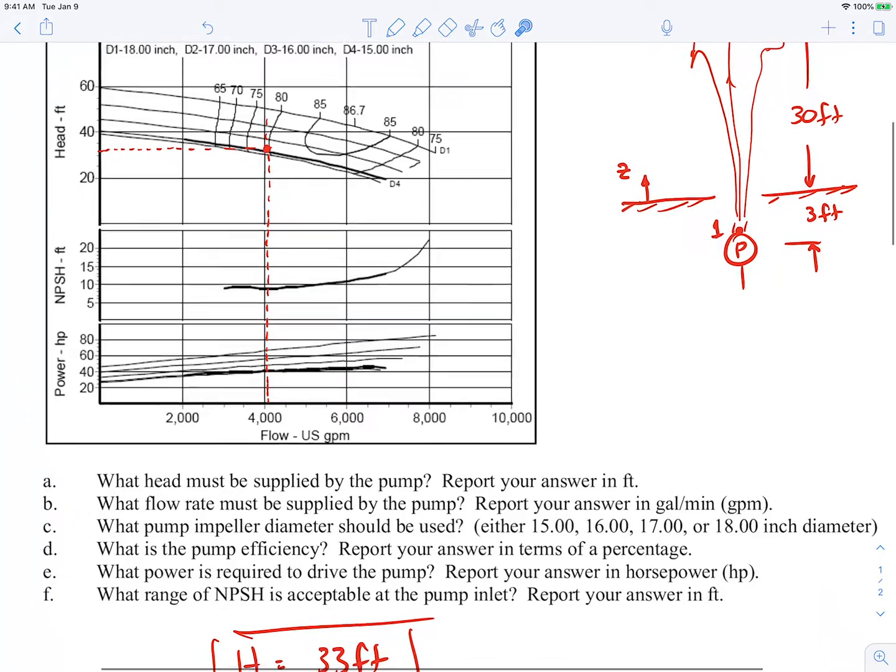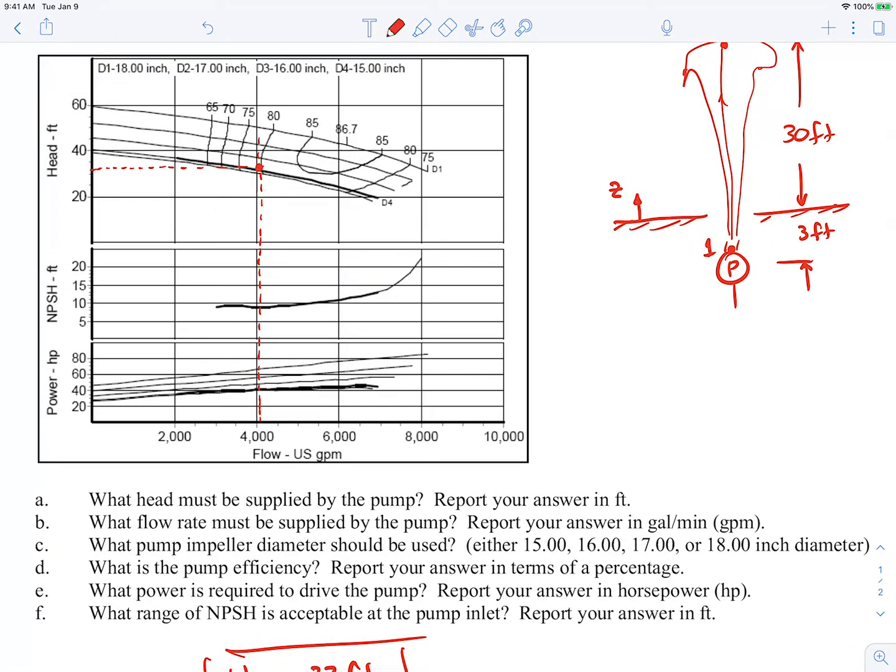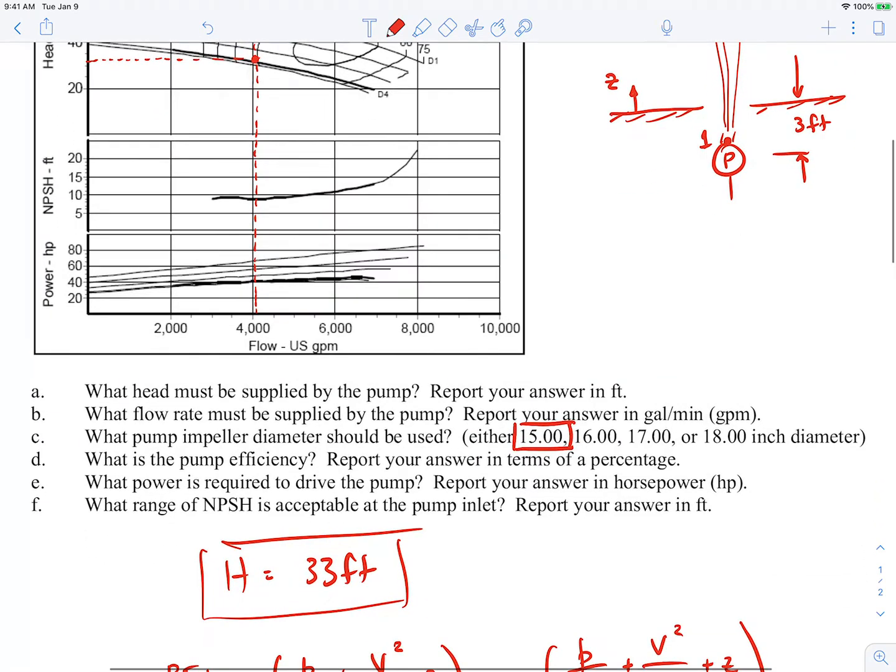So our pump impeller diameter will be the 15 inch one, the D4. So that's the 15 inch pump impeller diameter. What's the pump efficiency under these conditions? Well, if we look at the efficiency curve here, it's about 80% efficiency. So I'll just call it 80% efficiency.